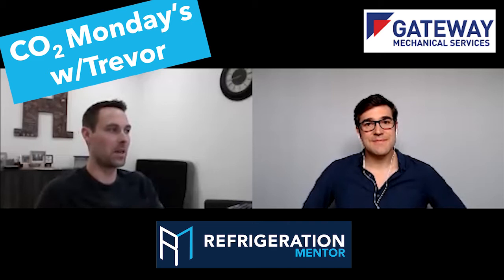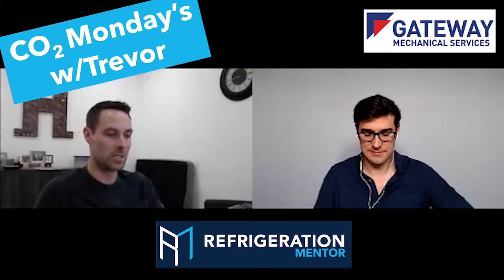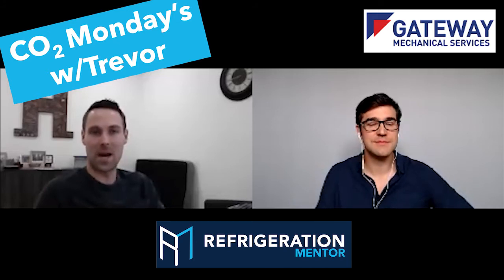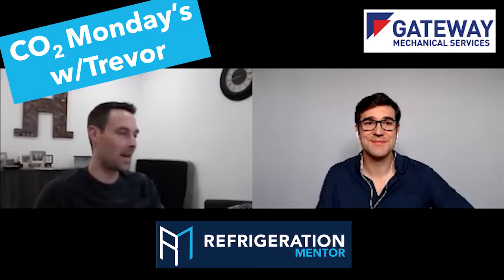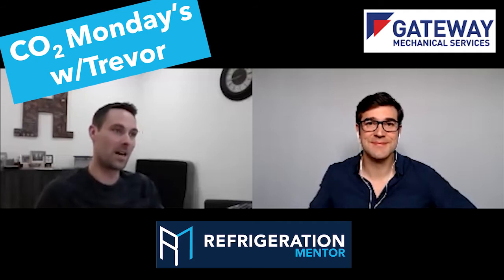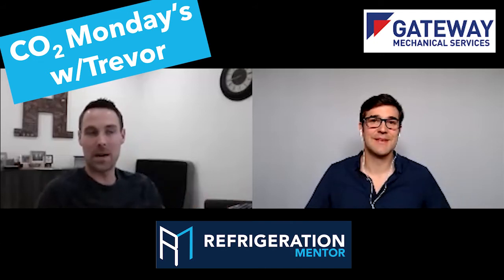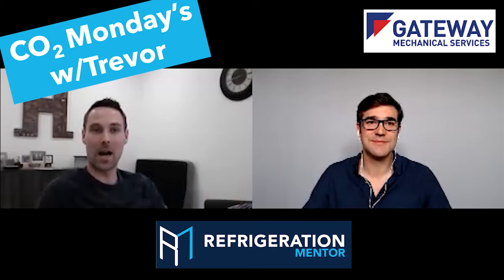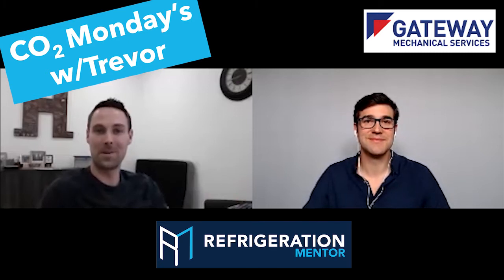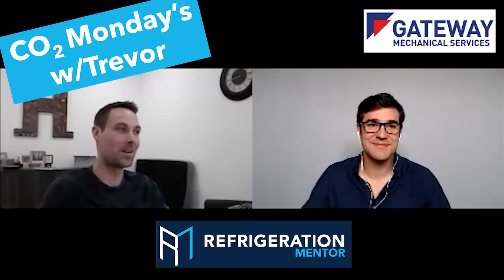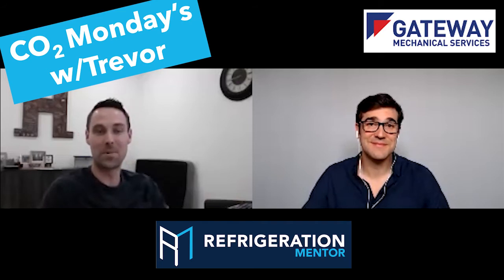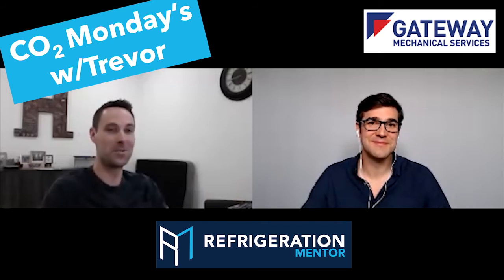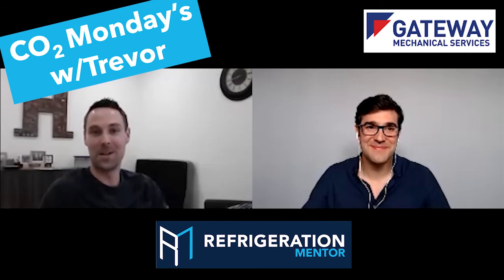Yeah. And the other really big thing I noticed different from going from HFC to CO2 is just really respecting the heat capacity. Holy man, I don't know how many times I've talked to guys, and I walk them through, okay, you're going to do this case repair, you're pumping it down. And everyone calls me back and says, I can't believe how long it took to pump down that system. With an HFC system, you can pump it down usually 20, 25 minutes if you manipulate some things at the rack. All of a sudden you go to CO2, you can be well over an hour to get the liquid out.